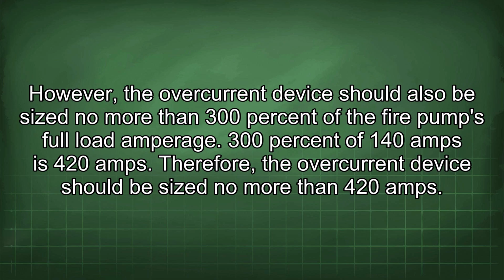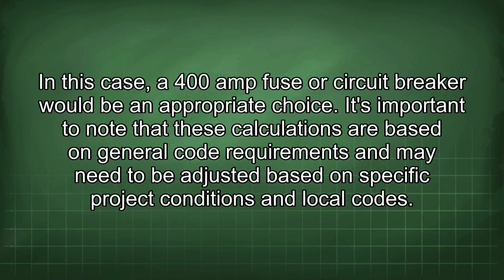However, the overcurrent device should also be sized no more than 300% of the fire pump's full load amperage. 300% of 140 amps is 420 amps. Therefore, the overcurrent device should be sized no more than 420 amps. In this case, a 400 amp fuse or circuit breaker would be an appropriate choice.